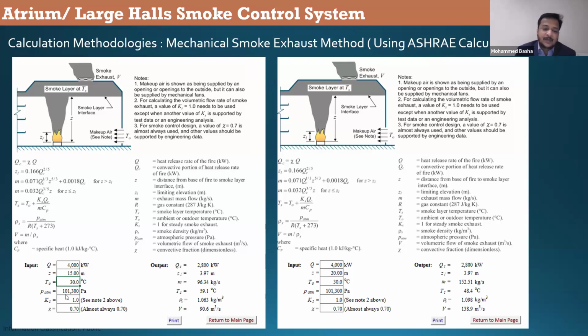So atmospheric pressure 1 bar, 101,300 pascals. This is pre-filled. Ks is 1. What is Ks? You can see here. Ks is 1 for steady smoke exhaust. The smoke exhaust is not variable. It's steady. Normally, the smoke exhaust will be steady. There is no variable frequency here. So, steady smoke exhaust.